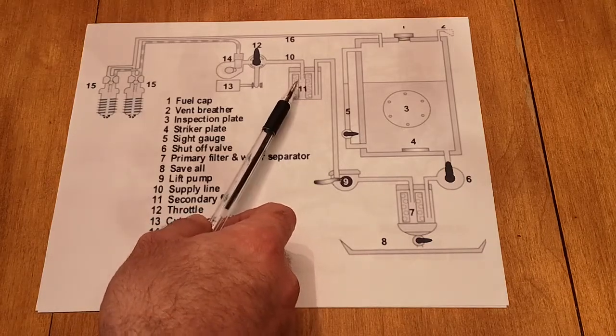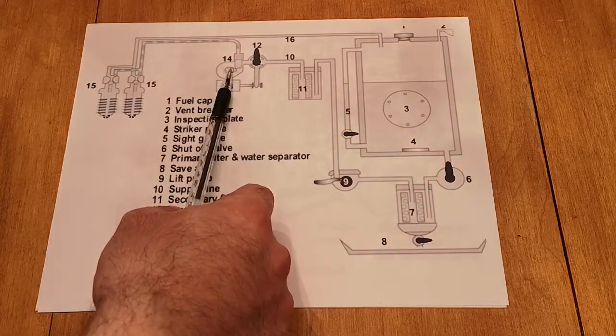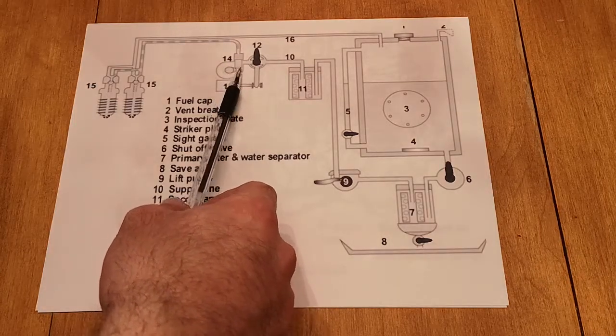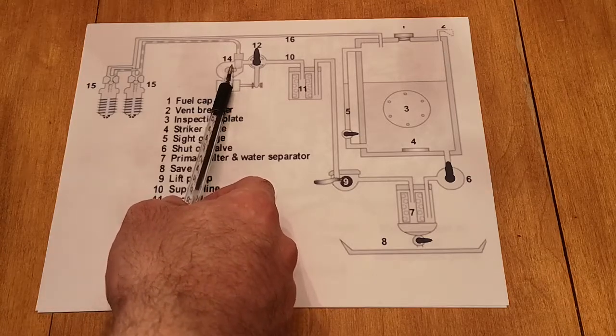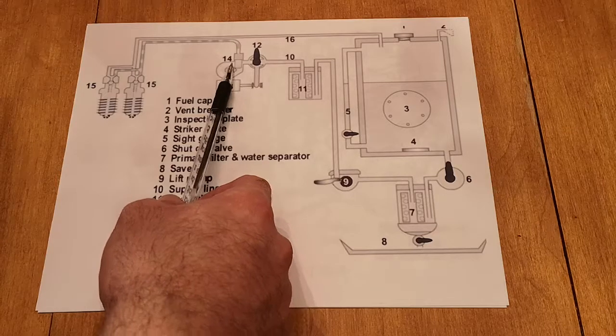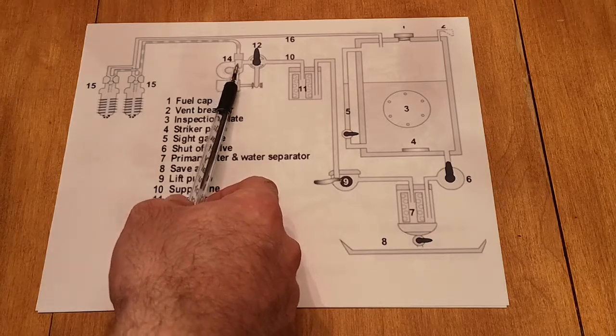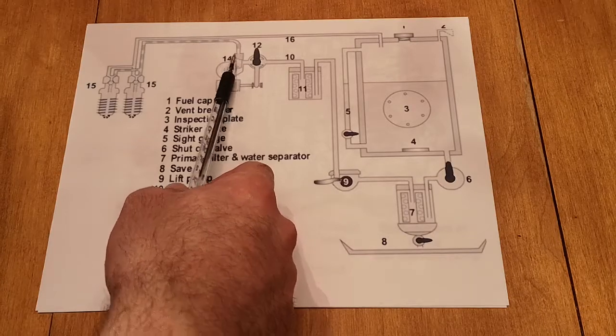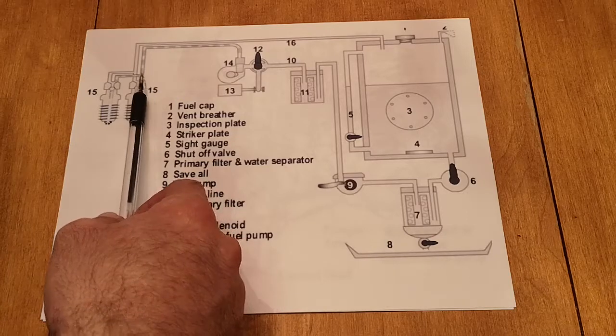The injection pump, port and helix specifically, will pressurize the fuel in its barrels and inject the fuel out through equal length, heavy walled, seamless steel tubing to the injectors.